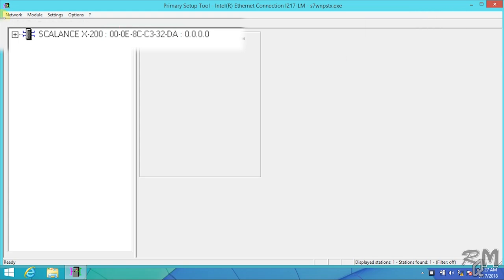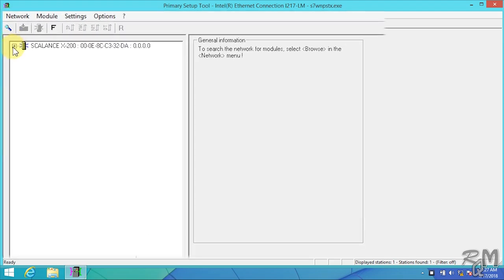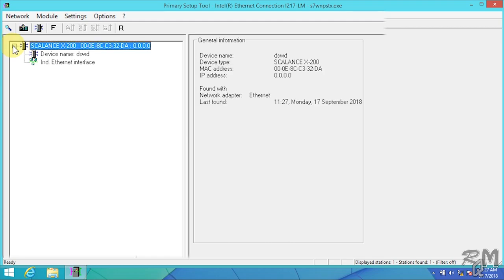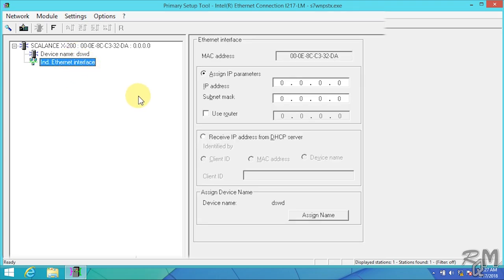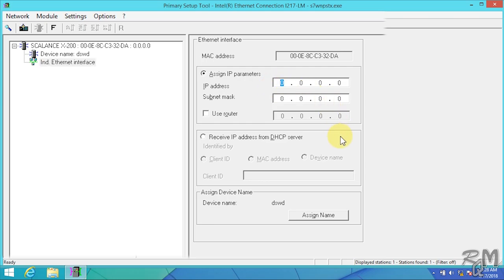After SCALANCE X200 you can see two addresses. First address is MAC address which you can find in front of SCALANCE switch. You can compare it with your connected SCALANCE switch to ensure that it is same. As you can see here both MAC addresses are same which indicates proper connection. Second address is IP address of device. Currently it is 0.0.0.0 which means IP address is not assigned to device.